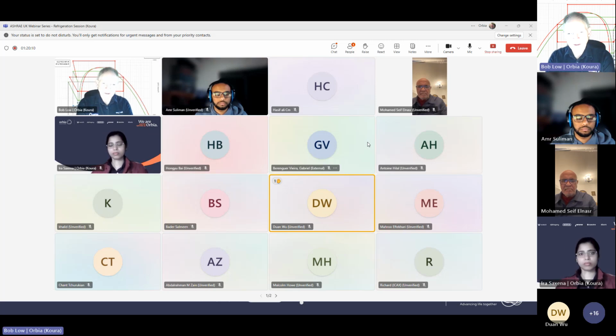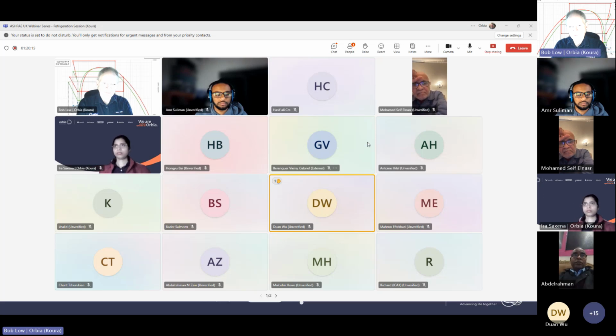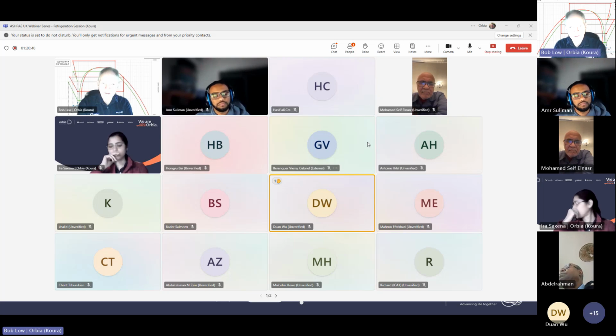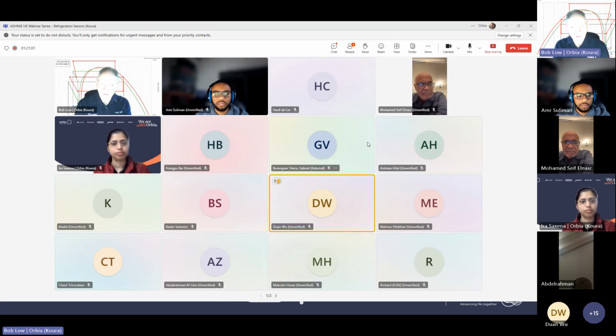So I think one of the more resistant markets, again because it's cost conscious, will be unitary air conditioning and small heat pumps, where again the cycle design and the equipment haven't really evolved very much in decades. And budget constraints mean that these guys will really resist even something simple like putting a bigger suction line pipe on if it adds to the unit cost. Because as long as you meet your energy efficiency requirements, there's no benefit in going above them. So if, say in America, you have a SEER 15 unit, you don't get any brownie points for SEER 15.1. You don't get any ticket price advantage in Walmart against your competitors at 15.0. And so the commercial drivers tend to damp down new technology adoption. But the GWP pressure, combined with an ongoing realization that you do need to focus on efficiency, I think we'll see evolution in that sector as well.